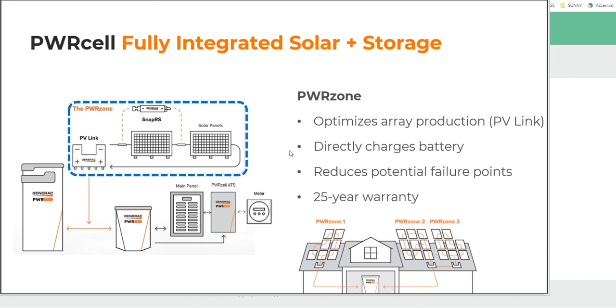Okay, again, I've talked about the power zone. I've talked about these being boost converters rather than buck converters. You can kind of see the specifications on this device. Something to think about: each one of these is rated at 2.5 kW. Anything above 2.5 kW, and one of the PV links is going to start clipping. So when you're doing design work, you kind of need to keep that in mind. Each one of these is 2.5 kW.